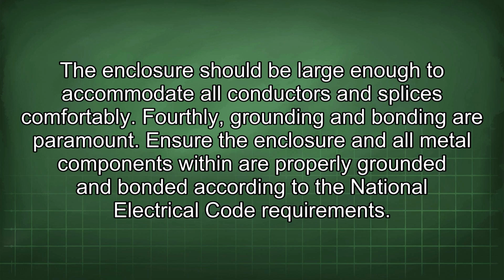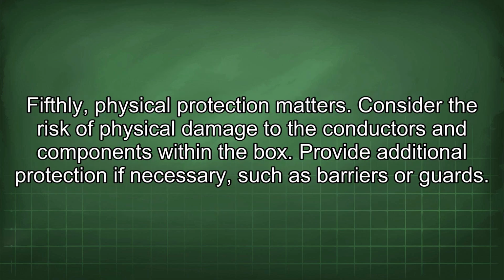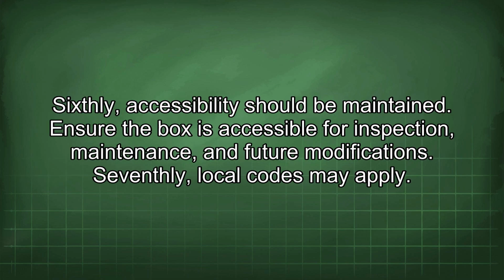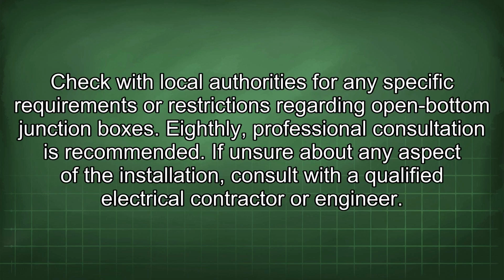The enclosure should be large enough to accommodate all conductors and splices comfortably. Fourthly, grounding and bonding are paramount. Ensure the enclosure and all metal components within are properly grounded and bonded according to the National Electrical Code requirements. Fifthly, physical protection matters. Consider the risk of physical damage to the conductors and components within the box. Provide additional protection if necessary, such as barriers or guards. Sixthly, accessibility should be maintained. Ensure the box is accessible for inspection, maintenance, and future modifications. Seventhly, local codes may apply. Check with local authorities for any specific requirements or restrictions regarding open-bottom junction boxes. Eighthly, professional consultation is recommended. If unsure about any aspect of the installation, consult with a qualified electrical contractor or engineer.